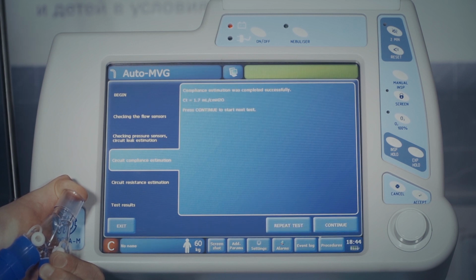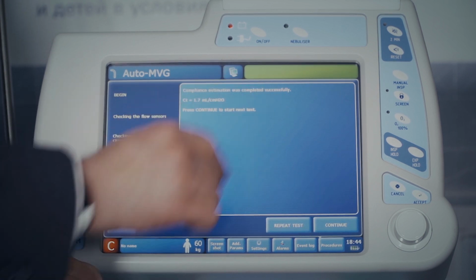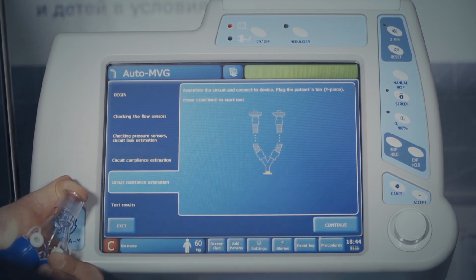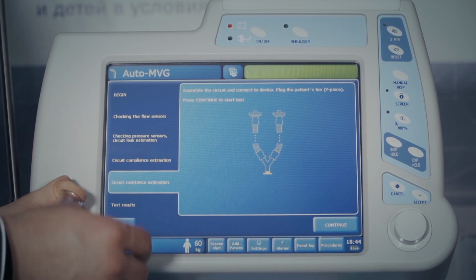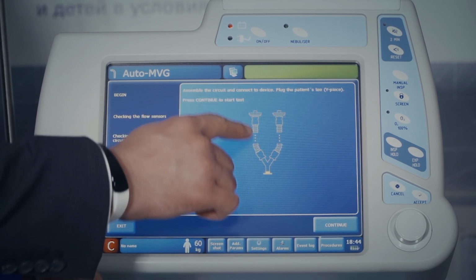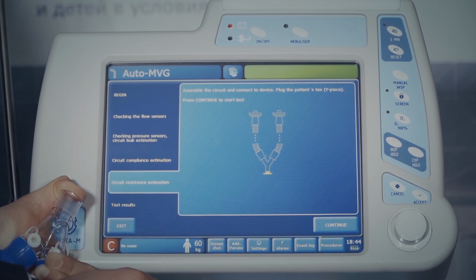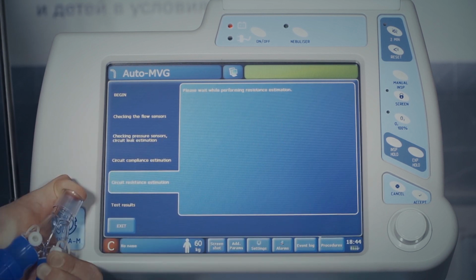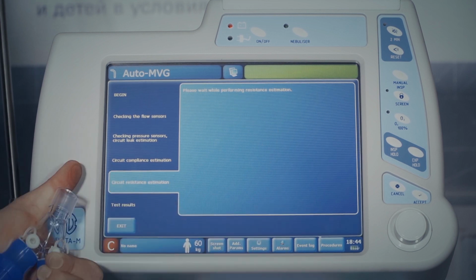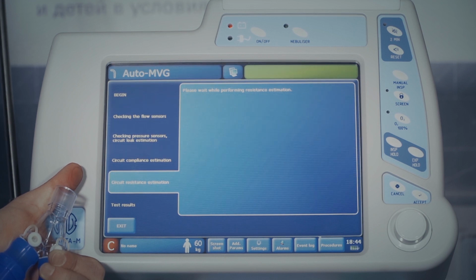The next test is breathing circuit resistance test. To start the test, press button Continue. Just like the two previous tests, the first part of this test shall be performed with Y closed from the patient's side. Upon completion of the first part, a request to open the patient's Y will be displayed on the screen. Press Continue and wait until the test is completed.